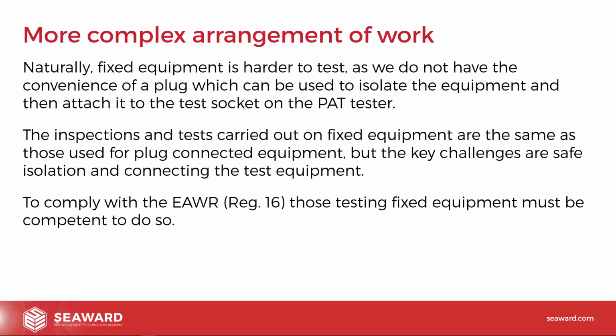Now, also mentioning on here competence to comply with the Electricity at Work Regulations, regulation 16, competence. Those testing fixed equipment must be competent to do so. So just be careful that you make sure that you are actually competent to test that equipment, because knowing the regulations and knowing how it's safe to do that does require that extra level of training. And if you're a PAT tester and you want to add fixed equipment testing to your portfolio, it's a good opportunity to get some extra training and get upskilled to be able to do that. There's a load more equipment there that you can get into, and you can generally charge more for testing that equipment.